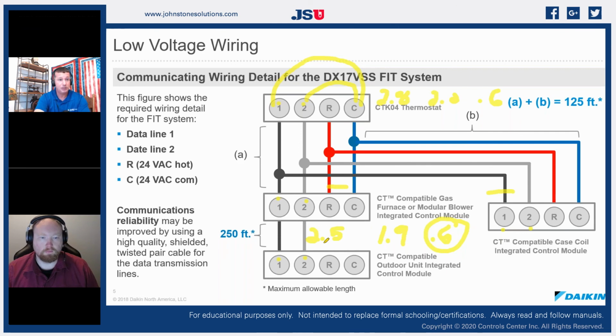We had a mouse that chewed into it. We had a staple that an electrician put into it. We had a piece of wire that was rubbing on ductwork. These things were not crucial when we had 24 volts AC, because we were still able to get our current through that conductor. Well, now that we're using 5 volts DC with a very, very low load, all of those things could affect the way our electrons flow through that control wire. So the thing that we are finding the most in the field is that if we have a change in that voltage, we've got a bad control wire. At that point, we are going to pull new control wire from our indoor unit to our outdoor unit, and that's typically where you find your fix.